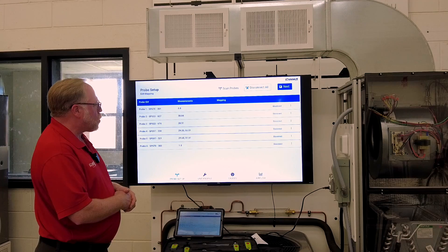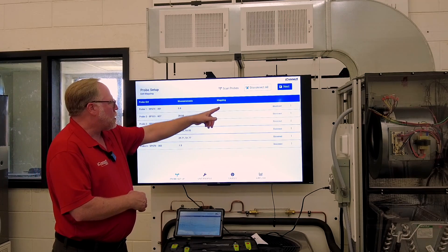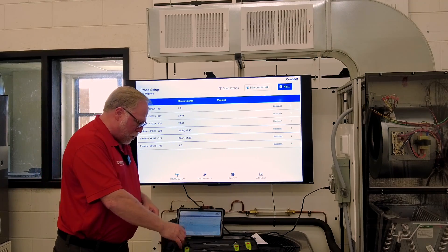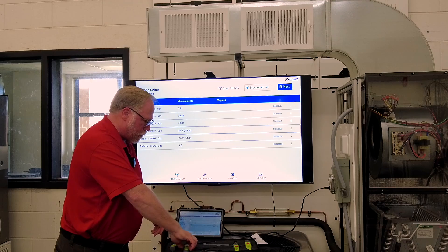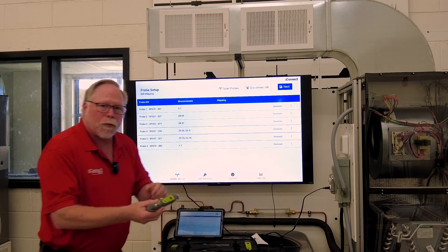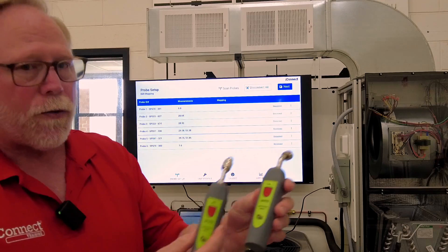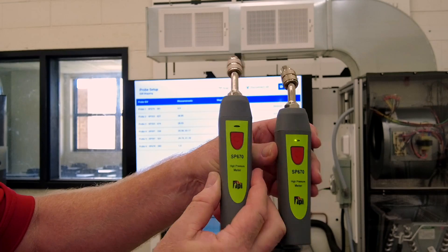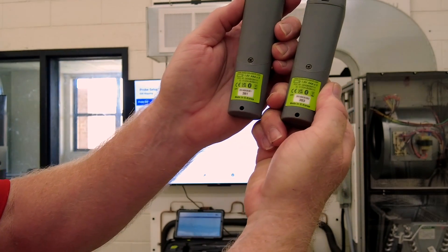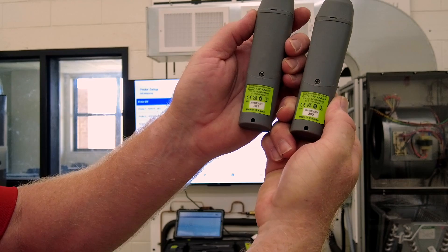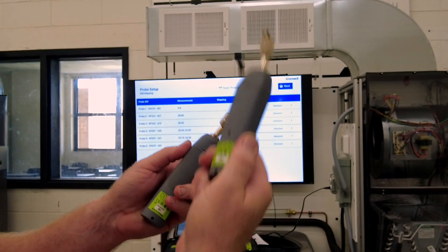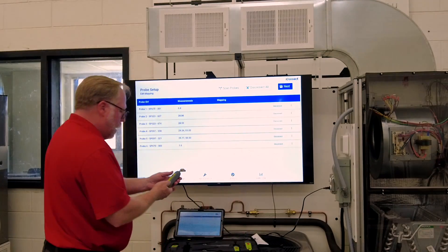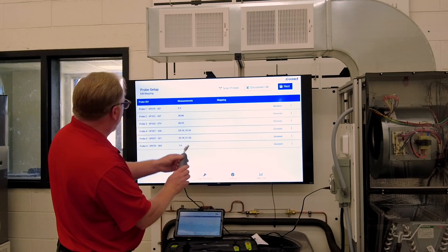The next thing we want to do is we want to map them to tell it which thing they are, high pressure, low pressure, supply air, return air, and so forth. Now when we do that, I want you to pay attention to something. You have duplicate probes here. So both of these are SP670 pressure probes, okay? But on the back, they have different serial numbers, a 381 and a 383. So we're going to tell the tablet which of these is high pressure and which of these is low pressure based off of that number.